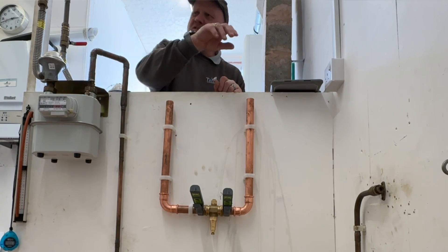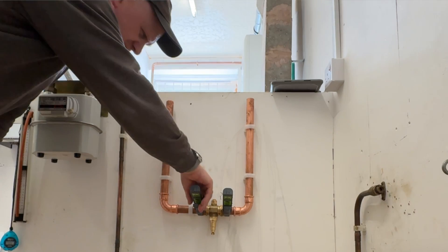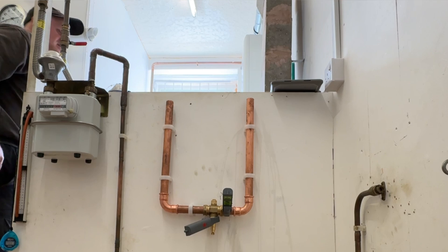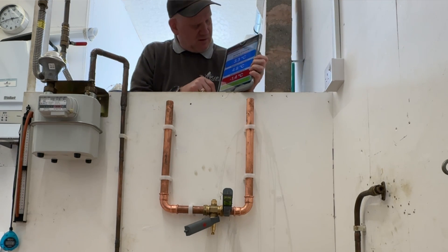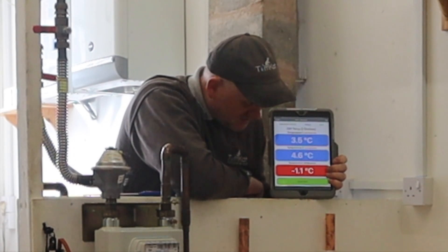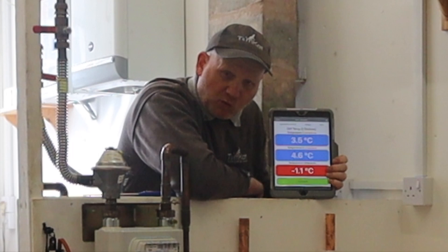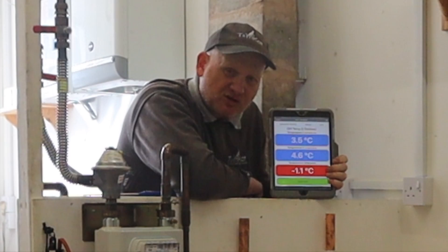Let's see what temperature the valve itself is. The valve itself is reading 4.6 degrees. So even though the water going in is minus 1.1 degrees, because of the copper it's causing us problems.